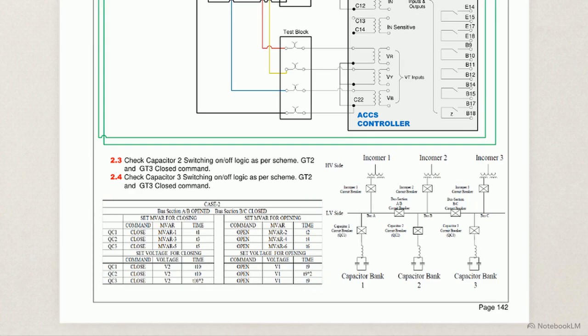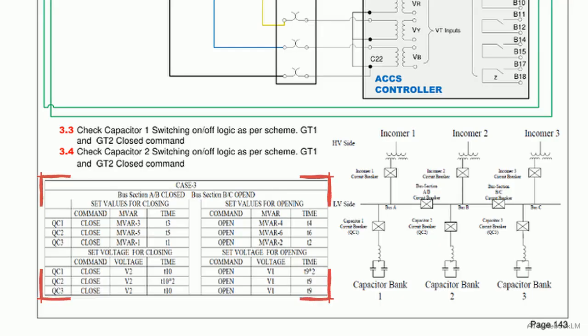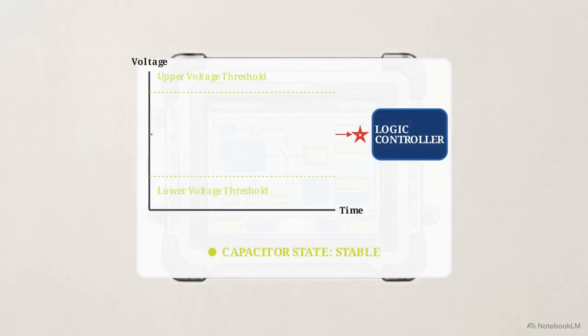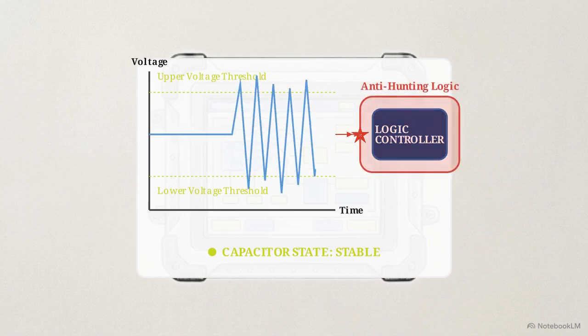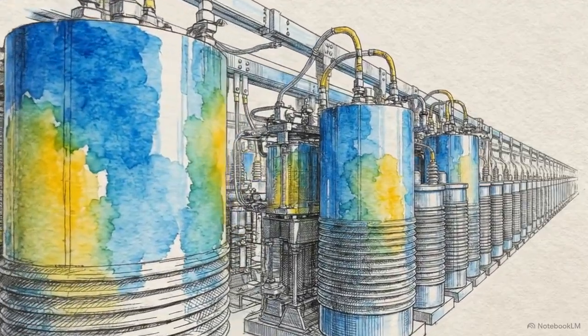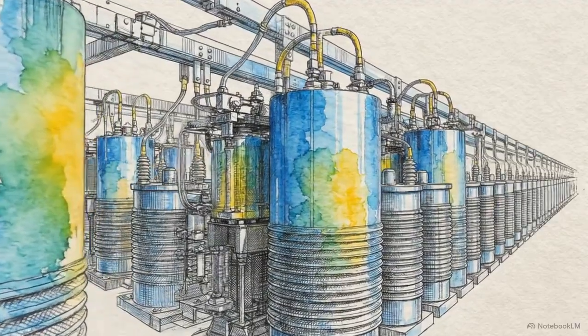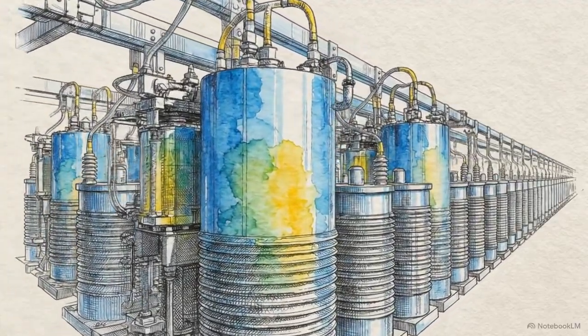the grid's reactive power. This logic table for Case 3 illustrates the specific MVAR settings used to verify the controller's response when bus section AB is closed and BC is open. During these validations, we also test the critical anti-hunting logic. We do this by deliberately fluctuating the injected voltage to see how the system reacts to erratic conditions. To pass this test, the ACCS must successfully block rapid, repetitive switching commands, ignoring the fluctuating inputs until conditions stabilize. Proving this anti-hunting logic ensures automated voltage stability for the grid, while simultaneously protecting the highly expensive capacitor banks from destructive physical wear and tear.